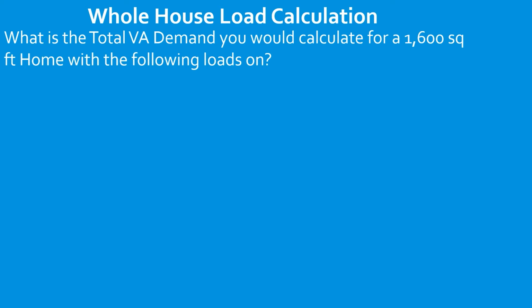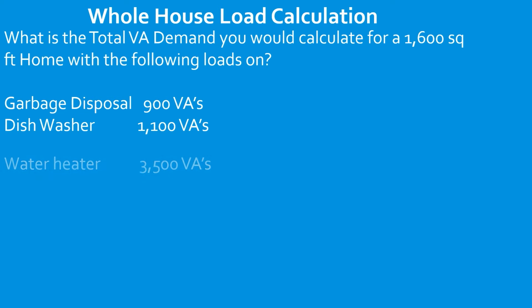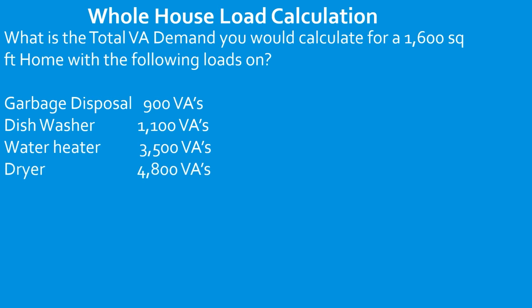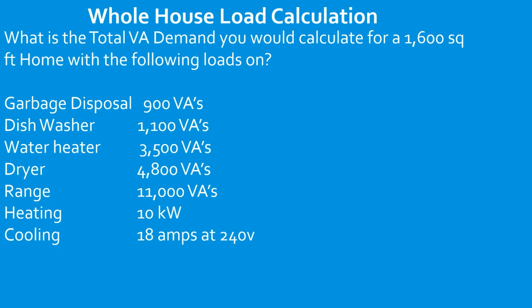What is the total VA demand you would calculate for a 1,600 square foot home with the following loads? So I just want to encourage you guys, everything you've learned up until this point, now it's all coming to the culmination. We're going to do a whole house load calculation. So we have a garbage disposal, dishwasher, water heater, dryer, range, heating, cooling, and you got some options. So we have 1,600 square foot.